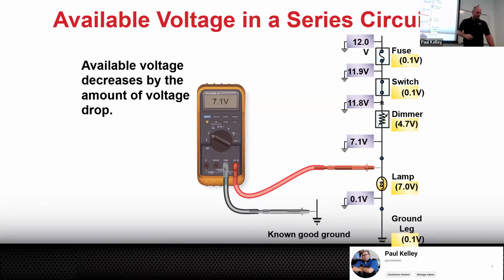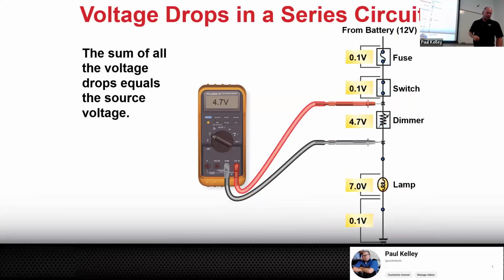When you voltage drop it, it's a similar test, just a little different style. You're not leaving the ground down here and poking, you're moving both of them. When you're voltage dropping, you're measuring the voltage drop between the red and the black. If you're measuring between the red and the black, you have to know what the expectation is.